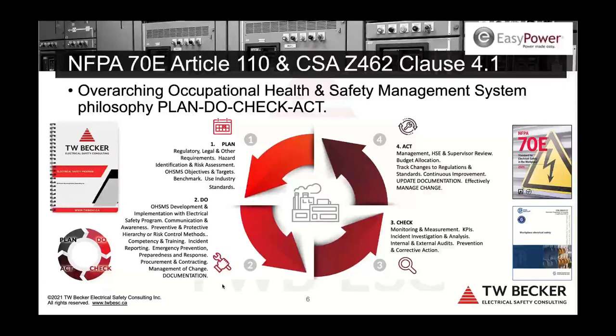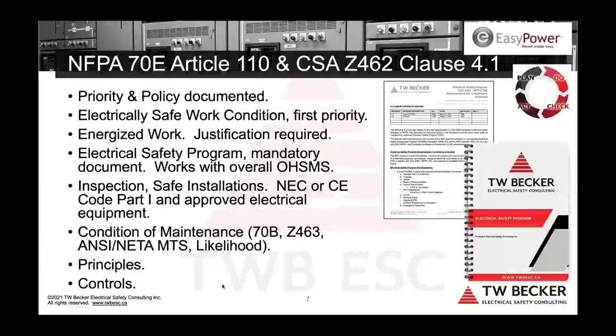All right, so again, 70E and Z462 mandatory requirements. Now, here are some slides with those mandatory requirements. Again, Article 110 or Clause 4.1 in Z462. Priority and policy must be documented in the electrical safety program. Using a procedural requirement, establish an electrically safe work condition. That's the first priority. But then we have justification for energized work documented. The program is, again, mandatory, and it works with the overall occupational health and safety management system.